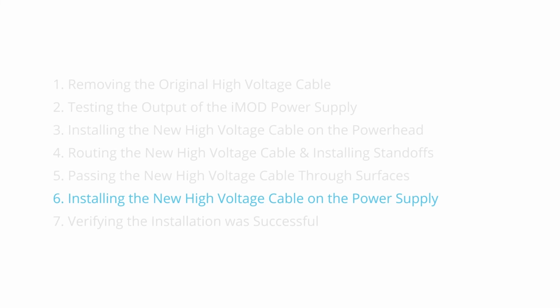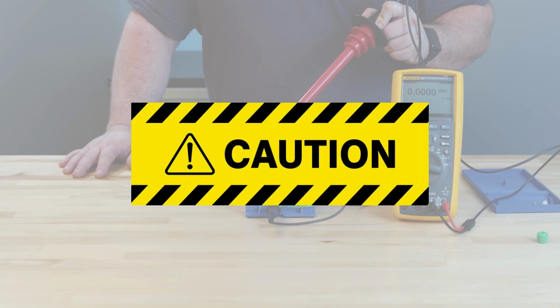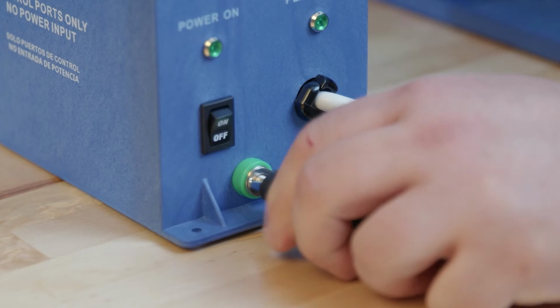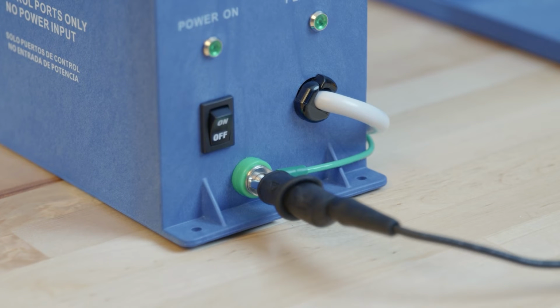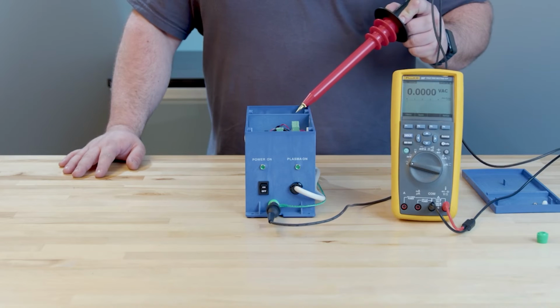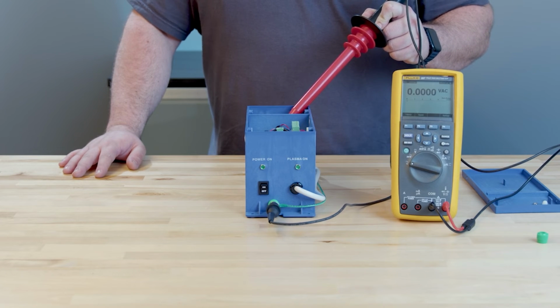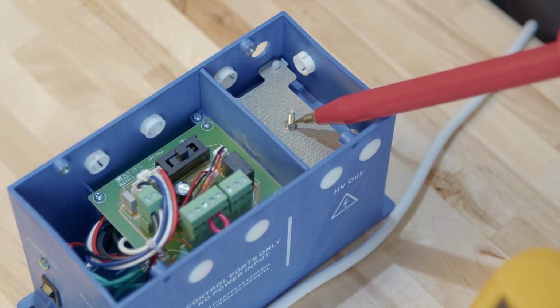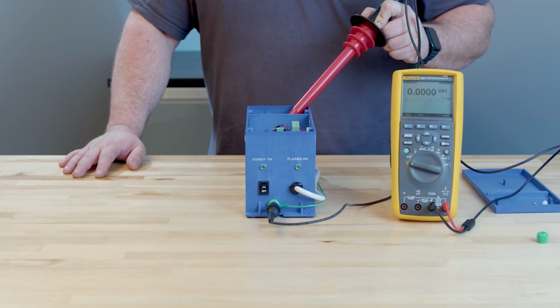Step 6. Installing the new high voltage cable on the power supply. Use caution when handling the GPS iMOD power supply, as it produces high voltage which can be dangerous if appropriate safety measures are not taken. If you have a high voltage probe, attach the grounding clamp of the probe to the grounding lug of the power supply. Confirm the power supply is still de-energized by checking the high voltage post with the voltmeter.